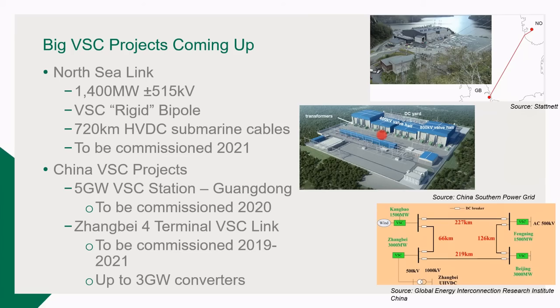But then we look at China. China's building some massive VSC projects. They've got a 5 gigawatt VSC station currently under construction. And the Zhangbei four-terminal VSC link, which will be commissioned over the coming year, is actually a four-terminal VSC with their own design of DC breaker. And you can see by the diagram here, these aren't small converters either. They're 3 gigawatts, 1.5 gigawatts with some reasonably long lines and the use of DC breakers. So there are CIGRE papers available on these kinds of projects.